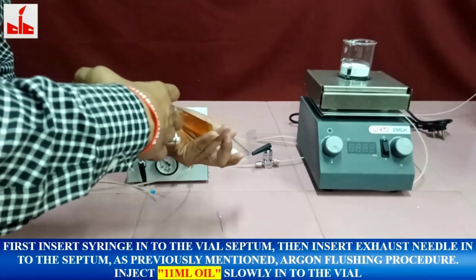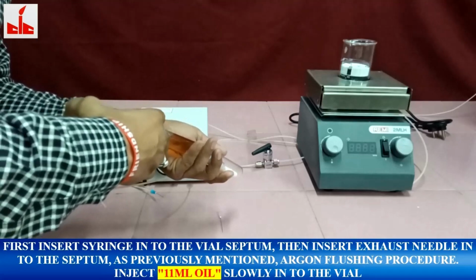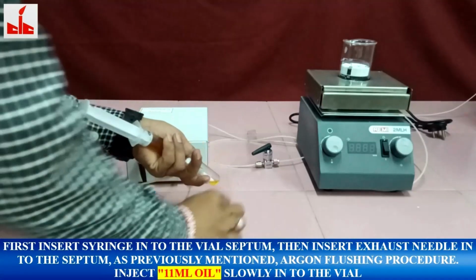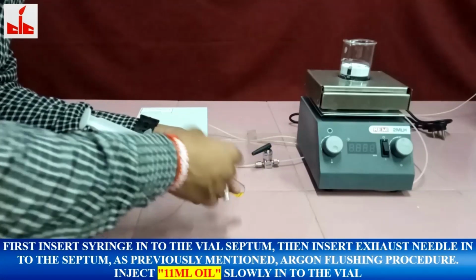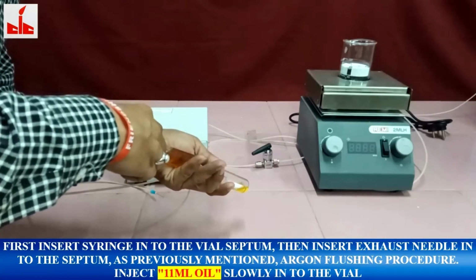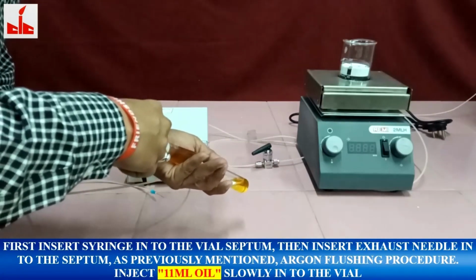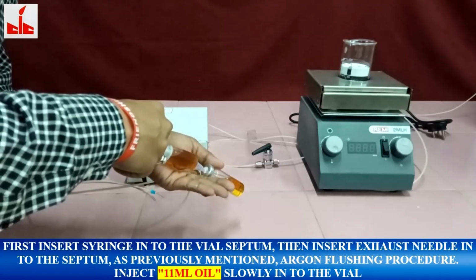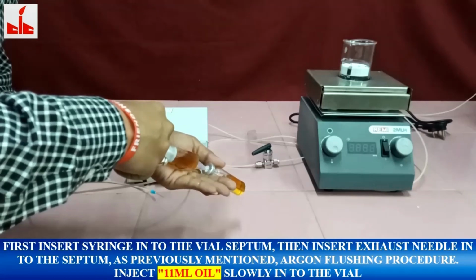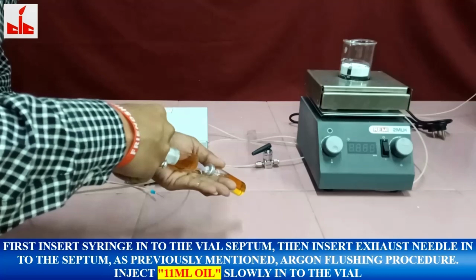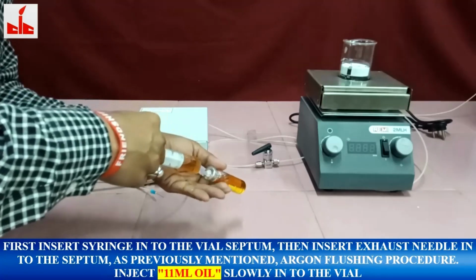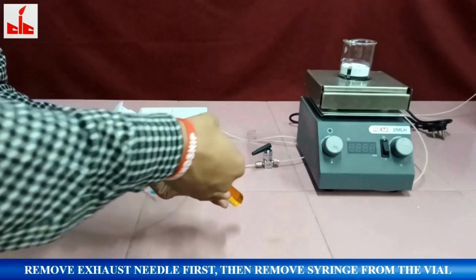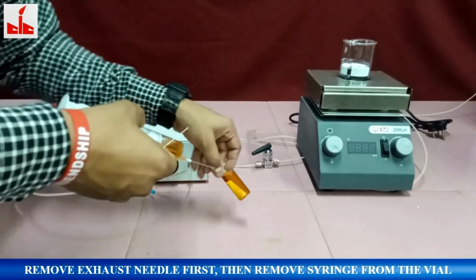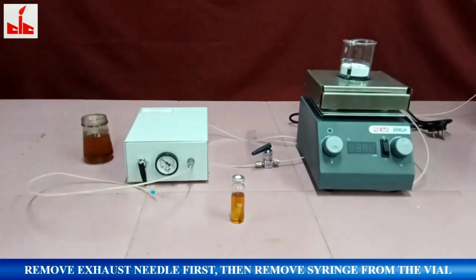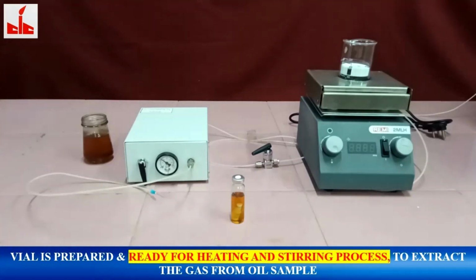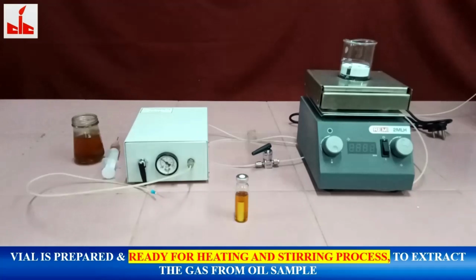First insert the syringe into the vial septum, then insert the exhaust needle into the septum, as mentioned previously in the argon flushing procedure. Inject 11 ml oil slowly into the vial. Remove the exhaust needle first, then remove the syringe from the vial. The vial is prepared and ready for the heating and stirring process to extract the gas from the oil sample.